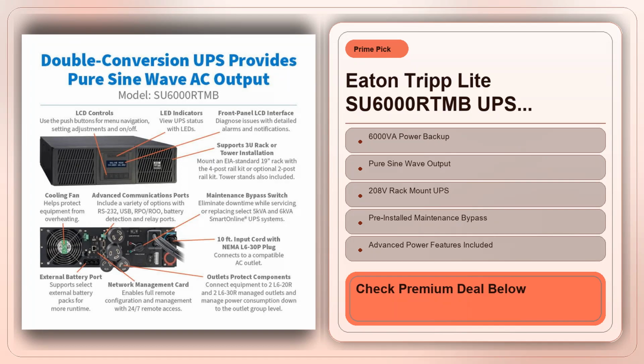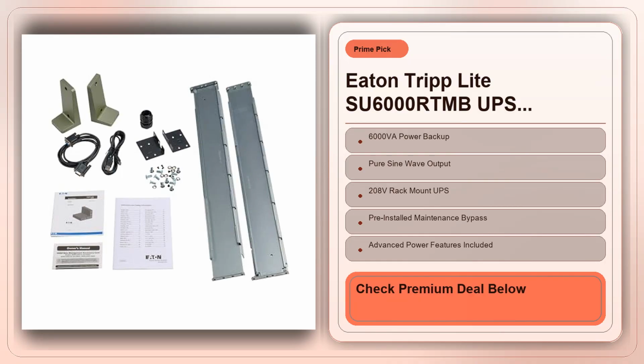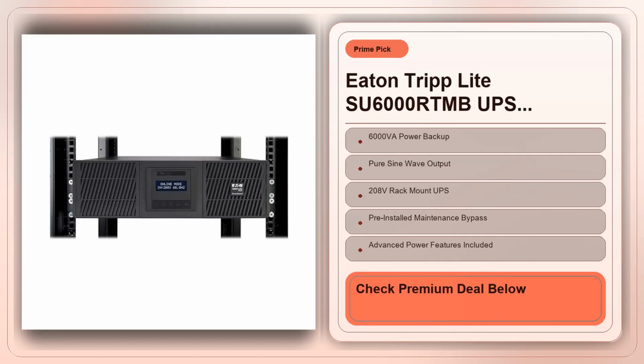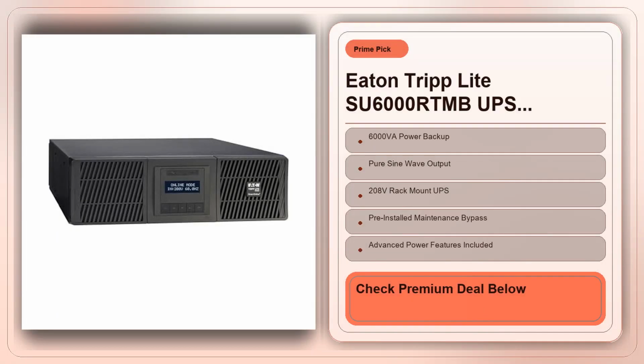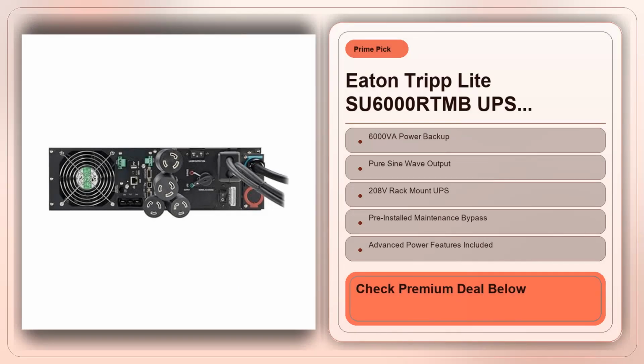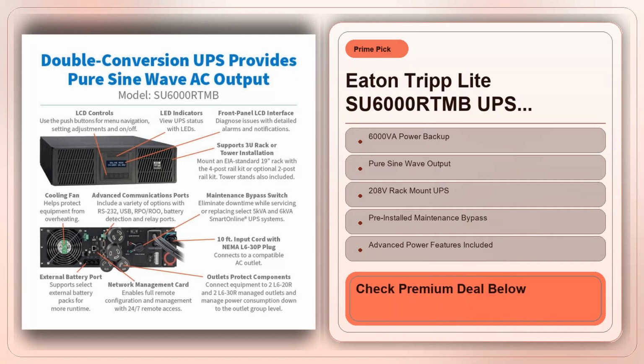The extended run rating, how long the batteries will hold the load after a loss, depends heavily on the actual wattage you're pulling. If you're close to the 5400W mark, you'll get roughly 5 to 6 minutes of backup, enough to shut down gracefully. If you're pulling a more modest 1500W, you could see 20 minutes or more. That's where the value really shines. You're paying for a UPS that can sustain a real, varied load, not just a static test bench figure.